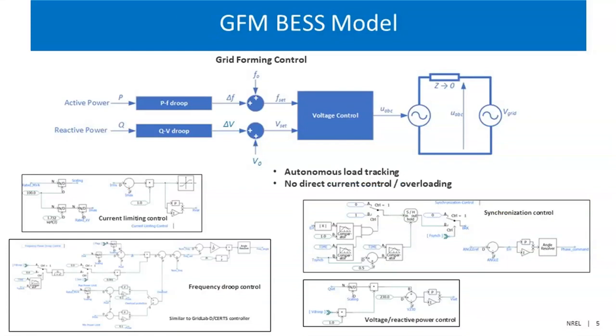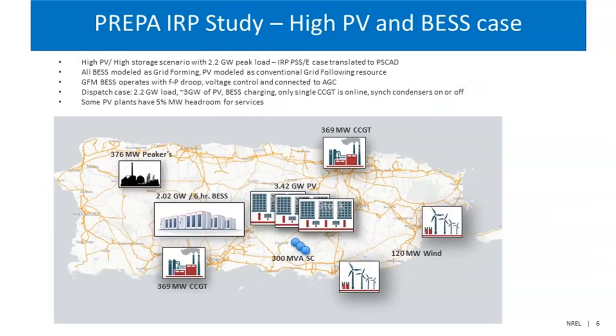In particular, grid-forming operation by inverter-based resources is, in a way, simpler because there are no things like a PLL. They have autonomous load-tracking ability. One limitation, of course, is the lack of ability to do current control. This is especially true when you go through a voltage fault event. In order to limit the current, you have to switch to a current limiting mode, and in that case you are no longer a grid-forming source anyway. So we have used this model and models of our renewable resources developed and validated at our facility to do a number of studies. This is one snapshot of one study we did for PREPA in Puerto Rico. This is the DOE-sponsored study looking at their very high-level penetration of solar.